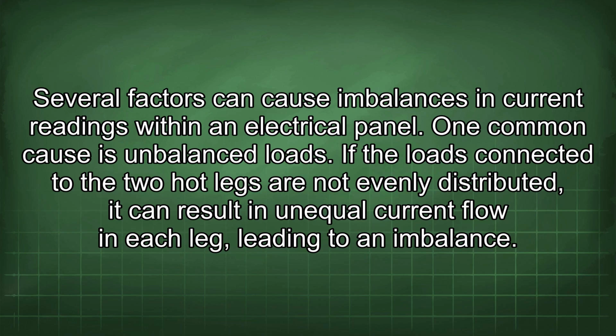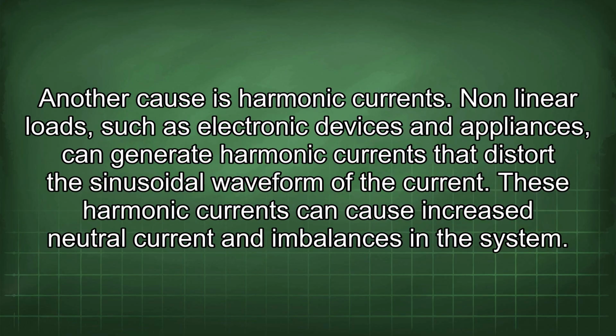One common cause is unbalanced loads. If the loads connected to the two hot legs are not evenly distributed, it can result in unequal current flow in each leg, leading to an imbalance. Another cause is harmonic currents. Nonlinear loads, such as electronic devices and appliances, can generate harmonic currents that distort the sinusoidal waveform of the current. These harmonic currents can cause increased neutral current and imbalances in the system.